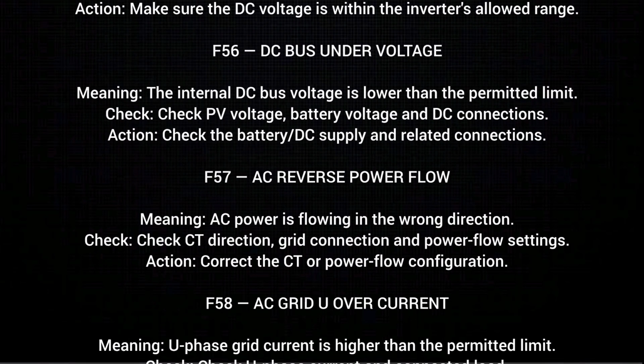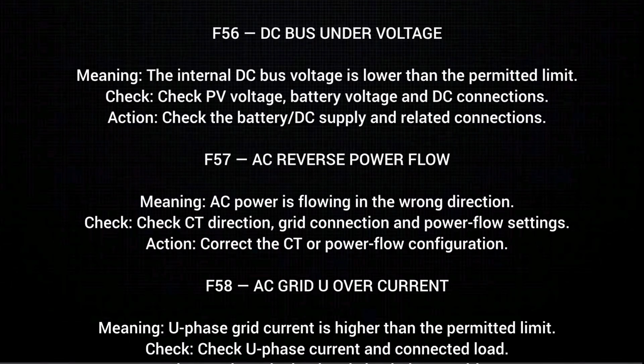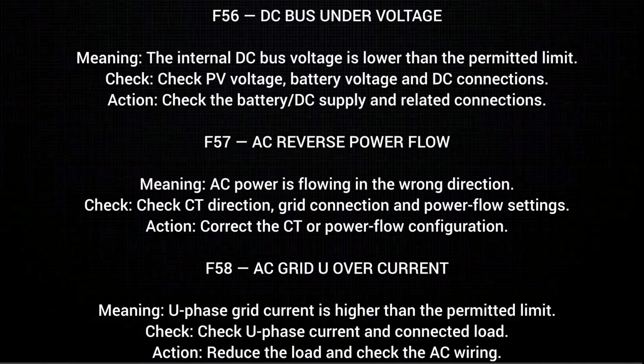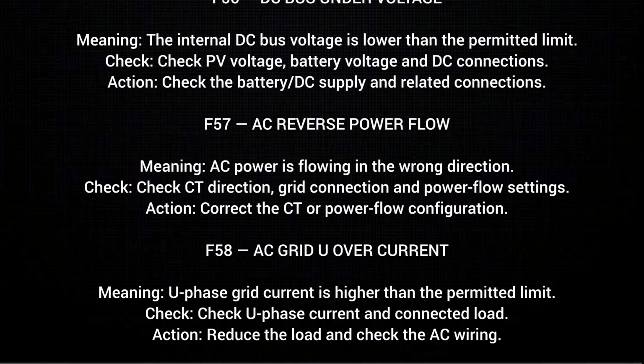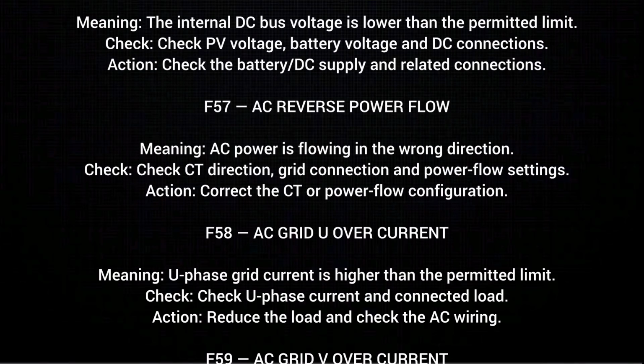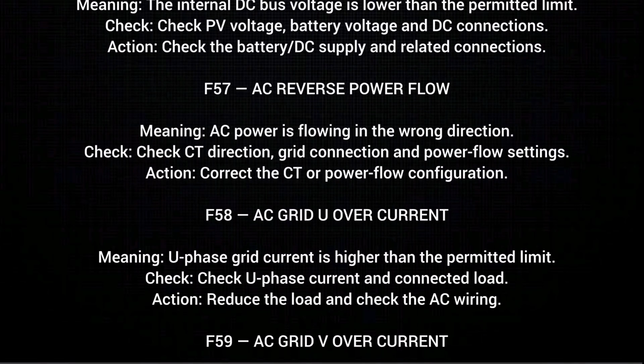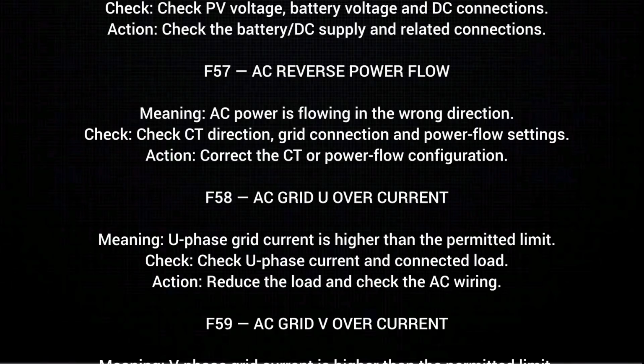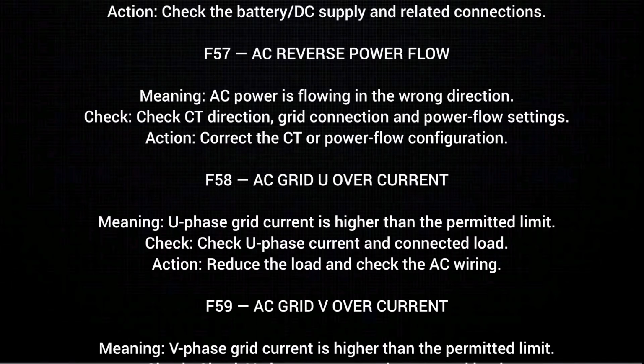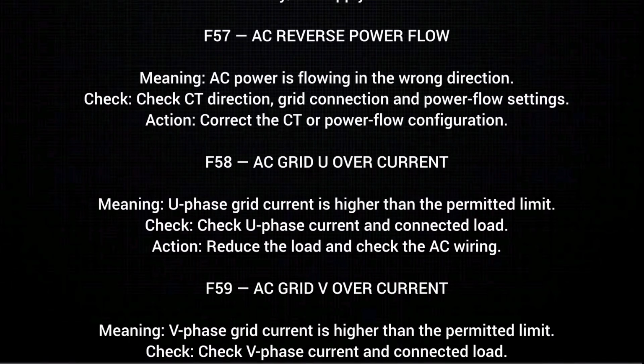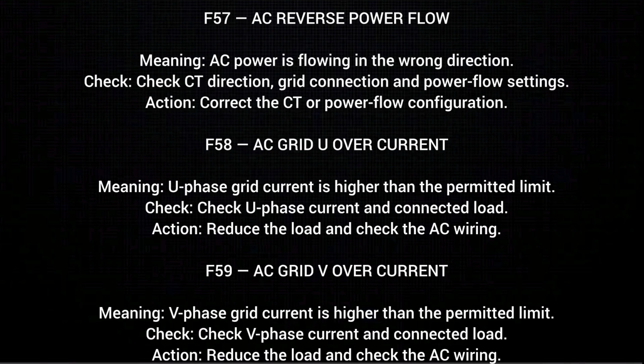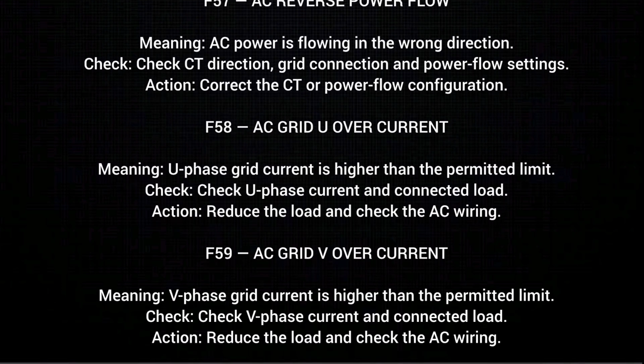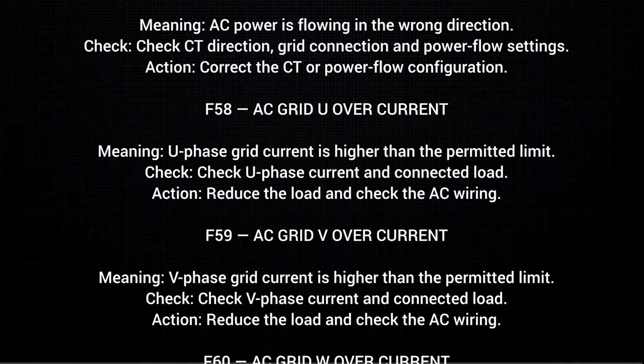F58. AC grid U over current, meaning U phase grid current is higher than the permitted limit. Check. Check U phase current and connected load. Action. Reduce the load and check the AC wiring. F59. AC grid V over current, meaning V phase grid current is higher than the permitted limit. Check. Check V phase current and connected load. Action. Reduce the load and check the AC wiring.